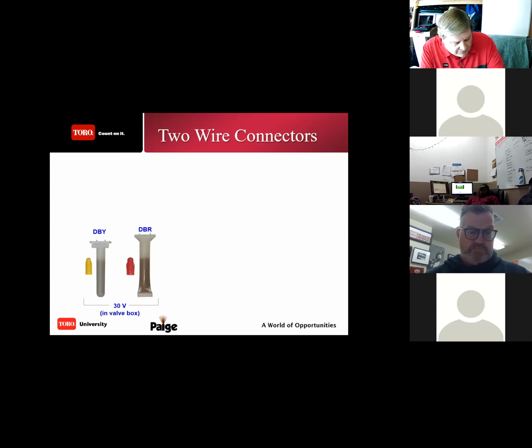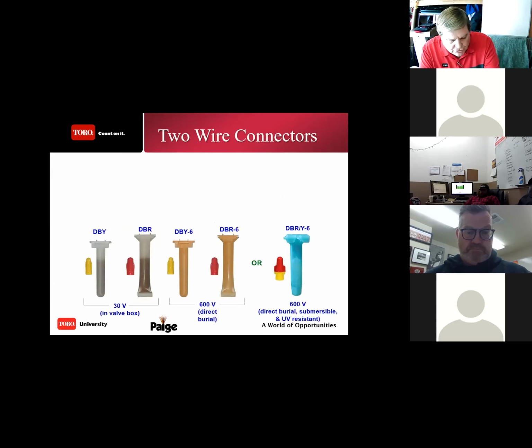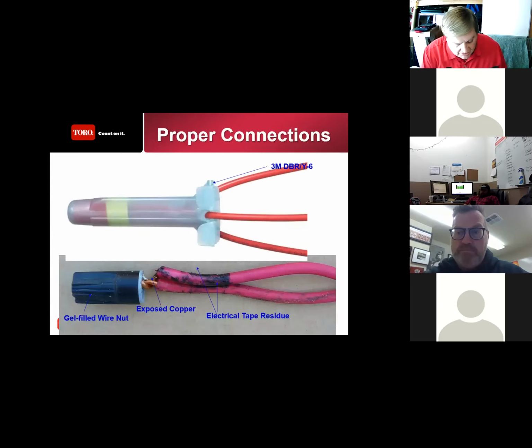So when looking at it, you have your conventional, you have your 2-wire, or now they have this light blue colored connector, which is designed to be able to handle either the yellow or the red wire connector together simultaneously. We thank our friends at Paige for providing us with this color page, showing us what we got. But the key, when doing your proper connection, the wire nut has to be buried completely to the bottom of the connector. Here's a bottom photograph. I've seen so many of these. You got this waterproof connector. Fine, it's gel filled, great.